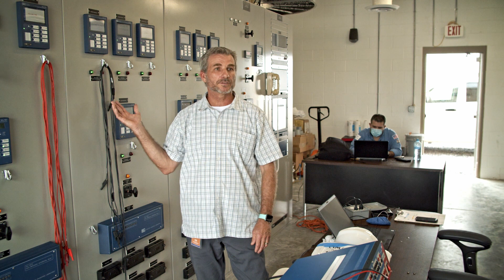Here inside the substation is where we have our control devices, the electronic relays that are the computers controlling the circuit breakers. We're able to use the data these devices collect to manage the grid, whether we have to open a circuit because there's a fault, or manage data to redistribute load and help manage where our load is going.